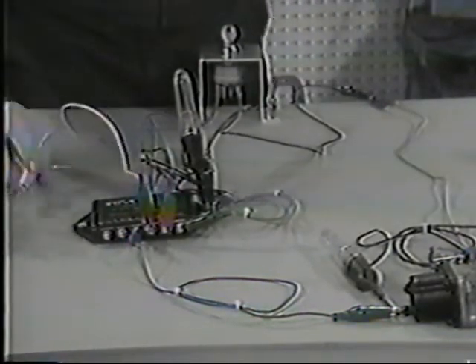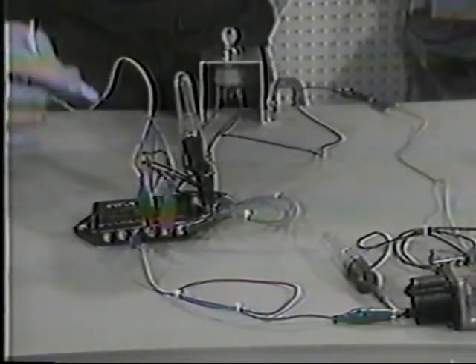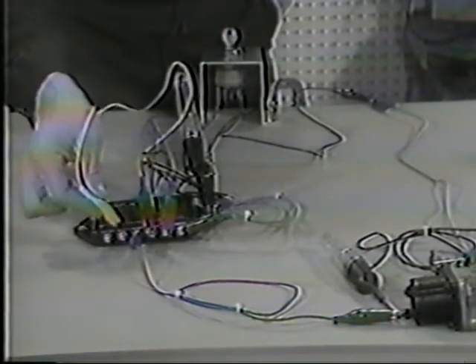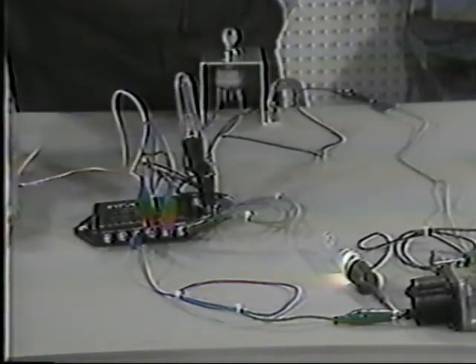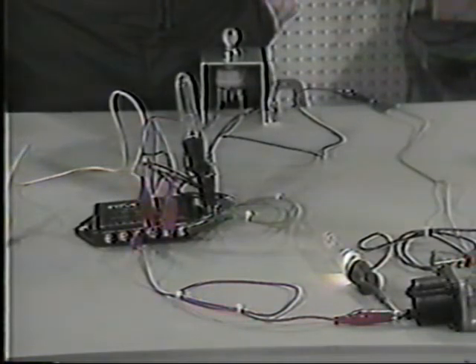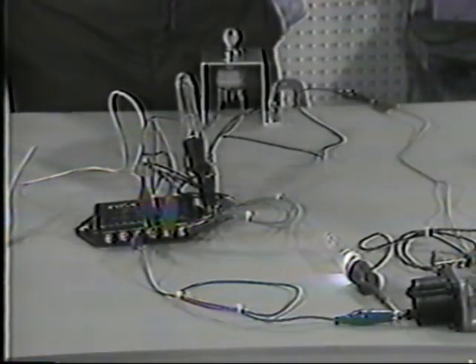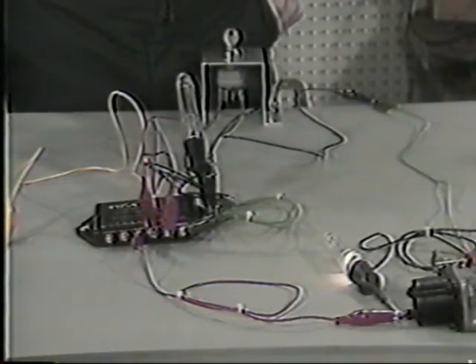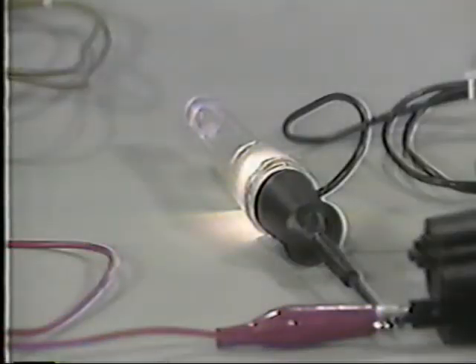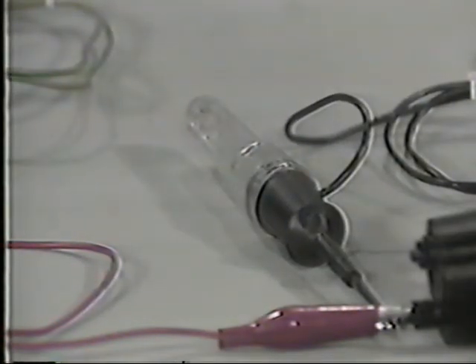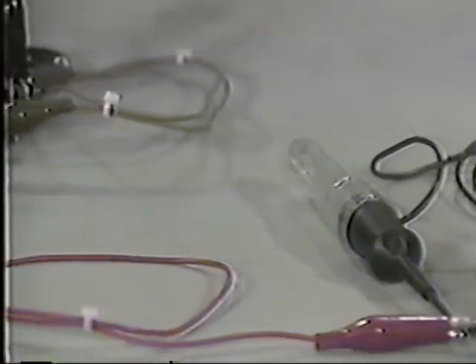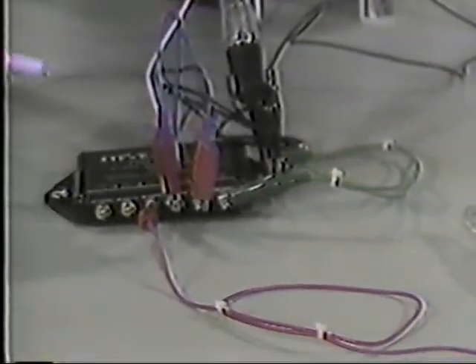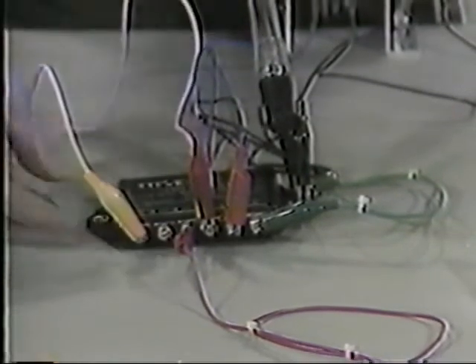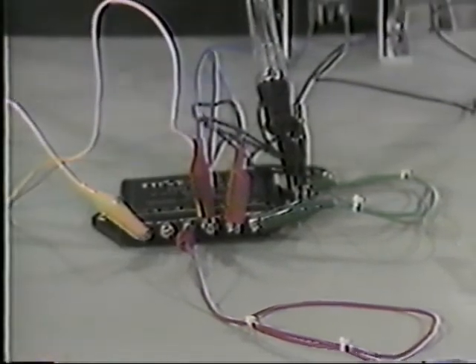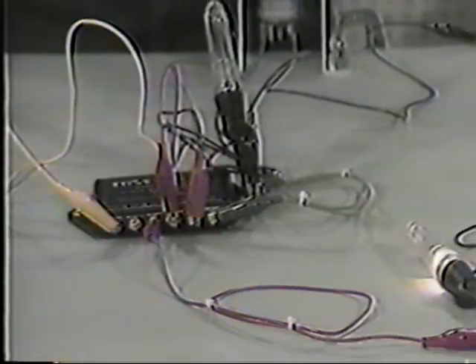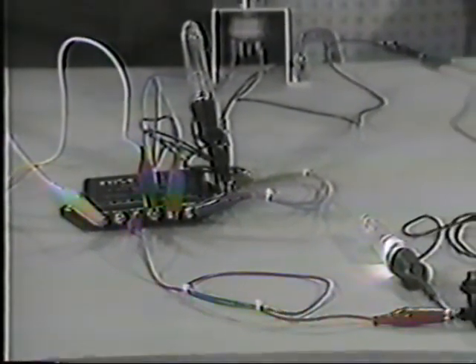First test, briefly touch the number 4 yellow jumper wire to post number 2. This simulates the start circuit input. The test light should come on, the fuel solenoid should come on for 20 to 40 seconds and should then turn off. Okay. Next step, take the yellow number 4 jumper wire and connect it to post number 1 and leave it there. The test light should turn on, the fuel solenoid should turn on and stay on. It should not turn off this time.